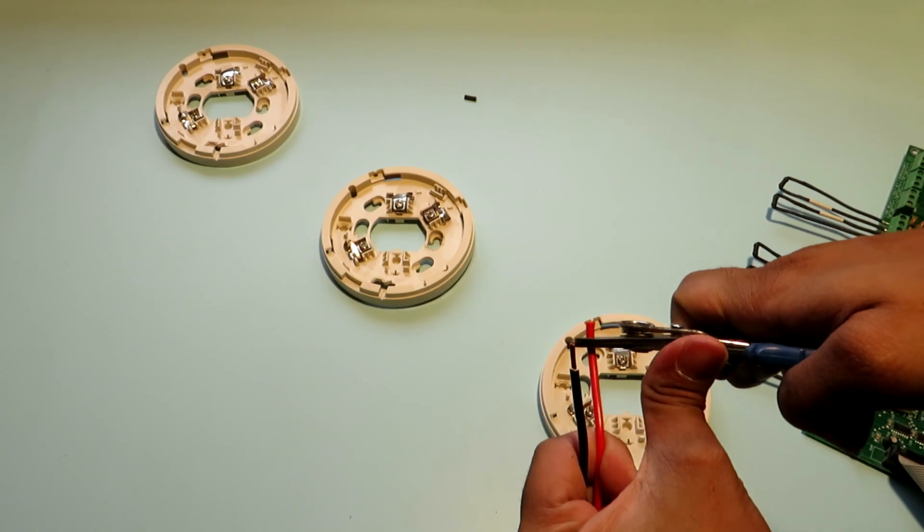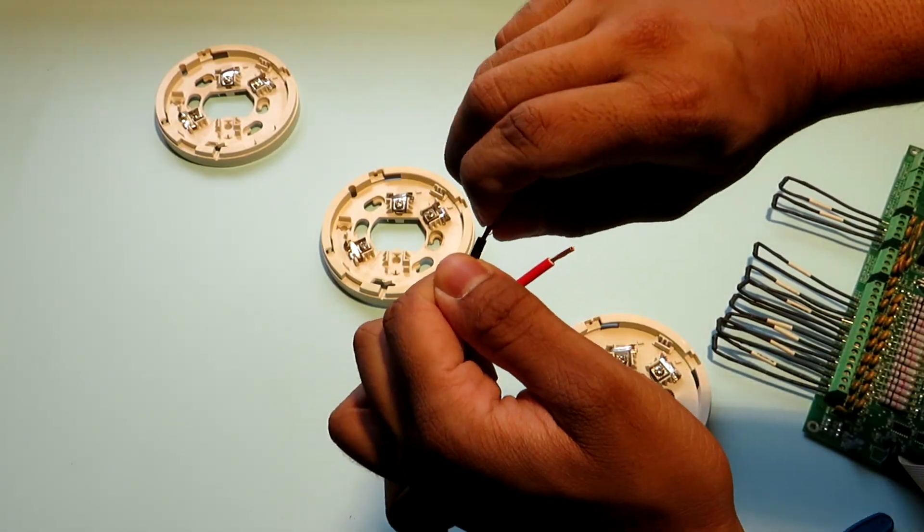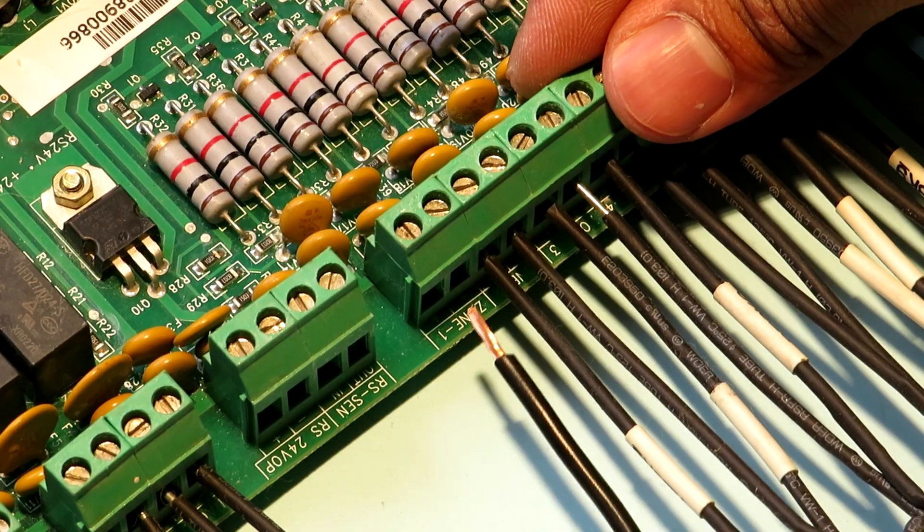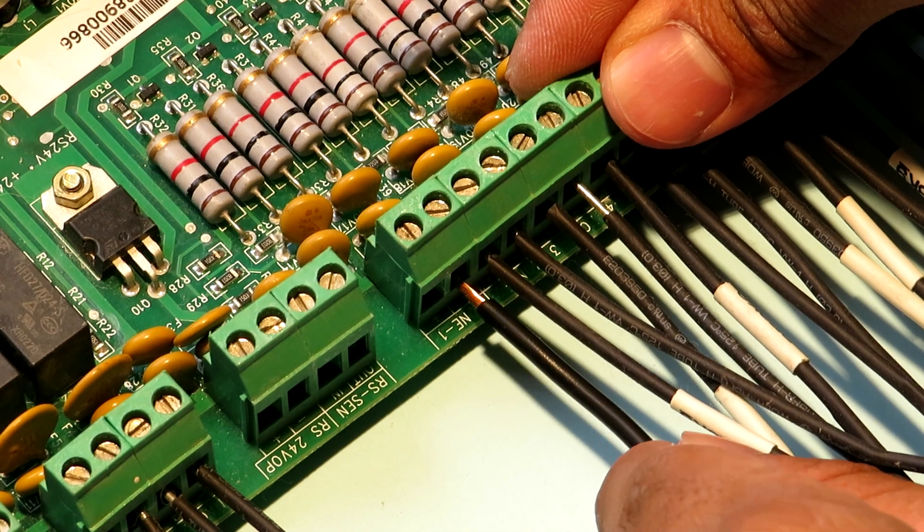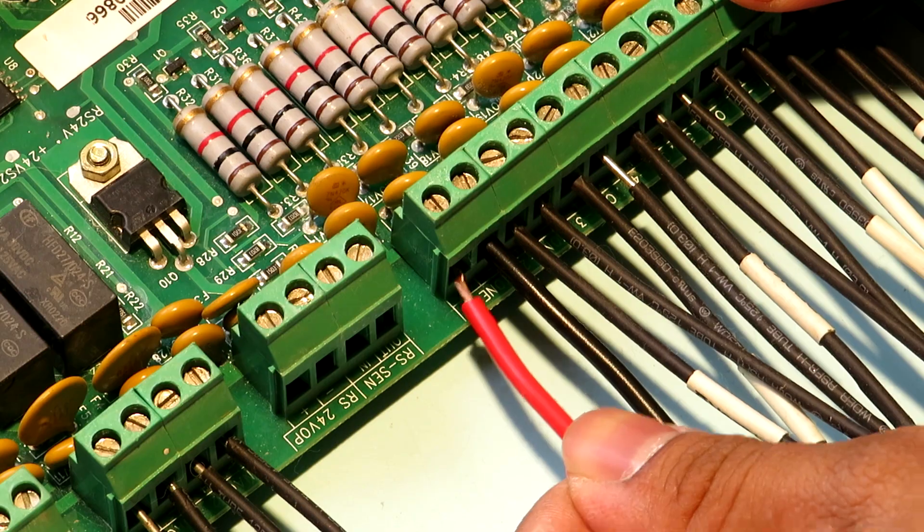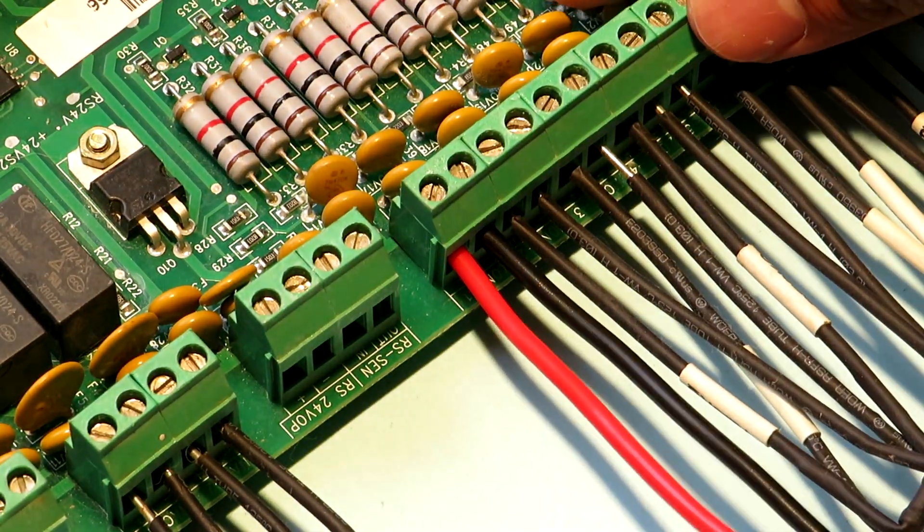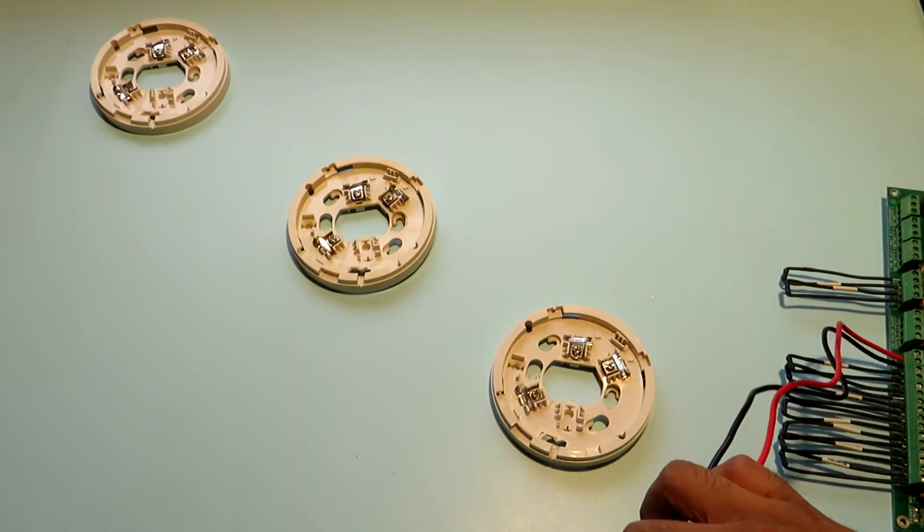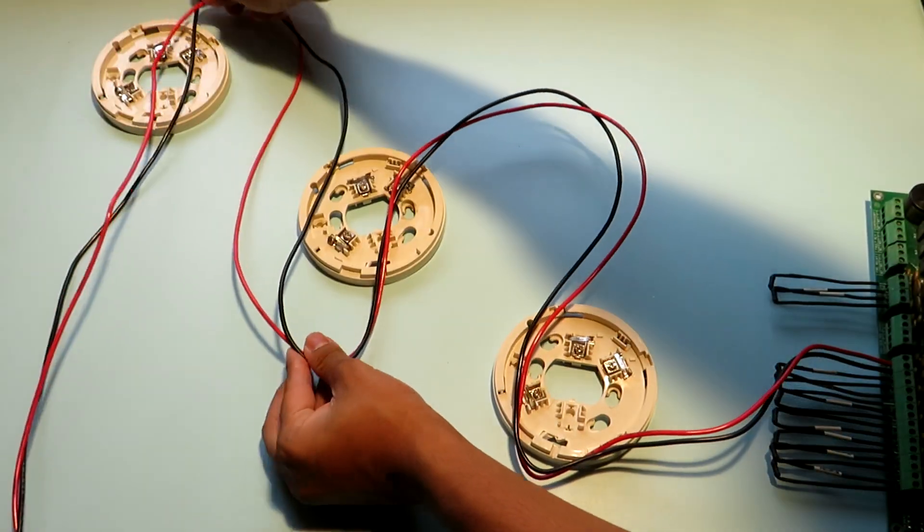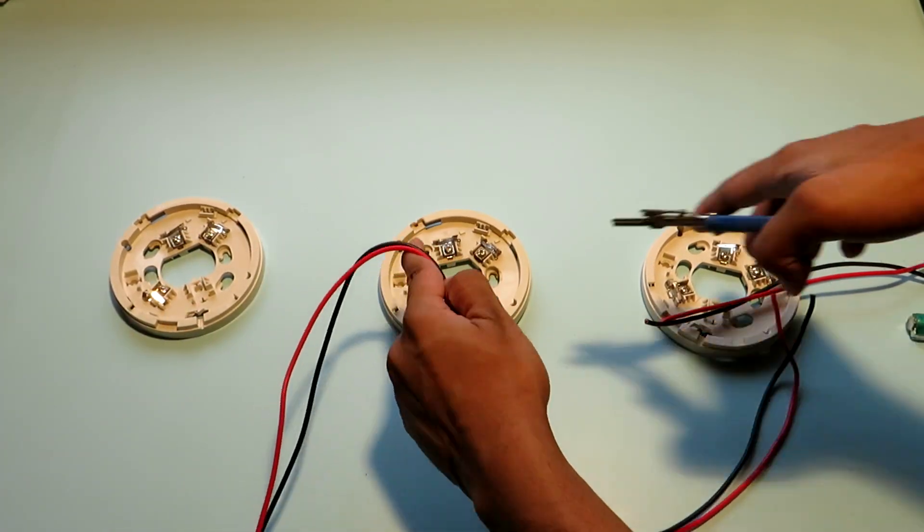So this is our positive and negative wire which will be connected to the zone input in our fire alarm control panel. Please ensure that you maintain correct polarity because this is not AC this is DC at 20 volts. That is the general voltage of smoke detectors. So this is a rough layout of how the wiring will go. We'll now cut the wires in these lengths so that we can make the connections.